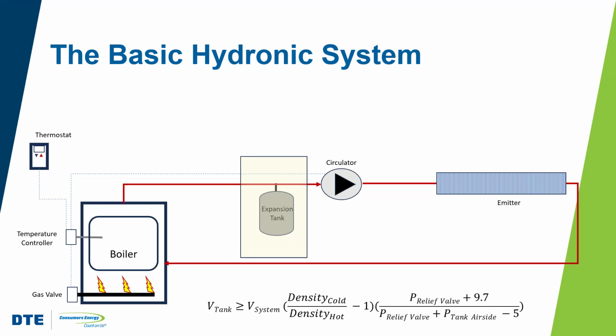is we want to make sure that it is properly sized for the system, right? So we're going to size that tank based on the air side pressure, based on the density of the cold water and the distance from the tank to the top of the system, right? And there's a formula for that. And there's also a 5 psi allowance, right? So in case there's any extra, there's some wiggle room there, right? And that 5 psi allowance allows the boiler relief valve to get about 5 psi lower than the rated operating pressure when the system is at its maximum operating temperature.